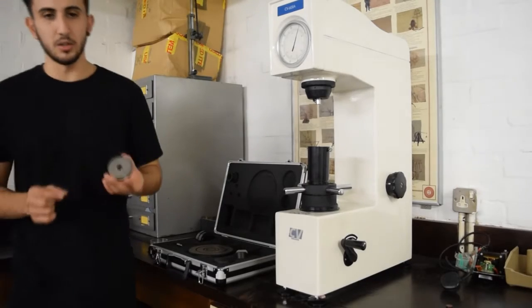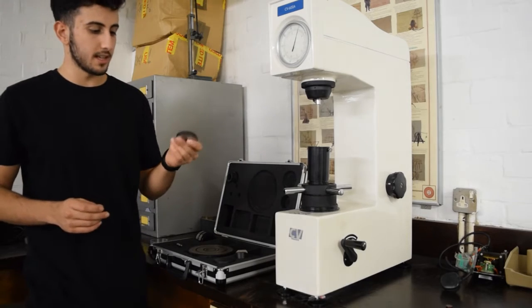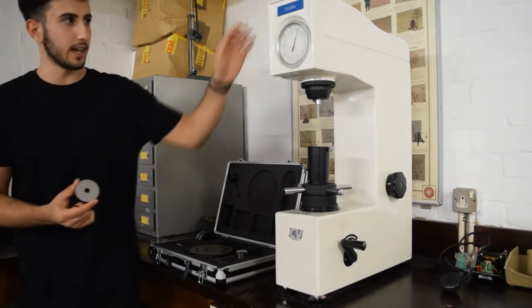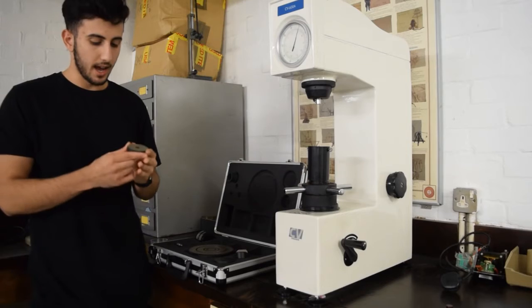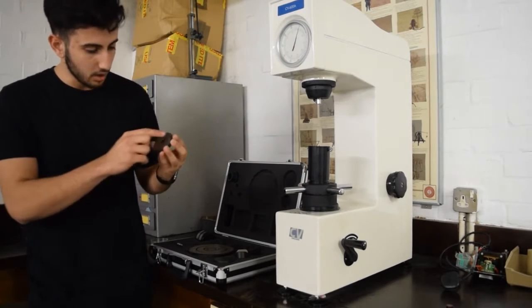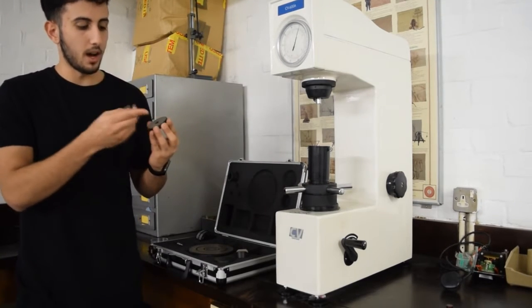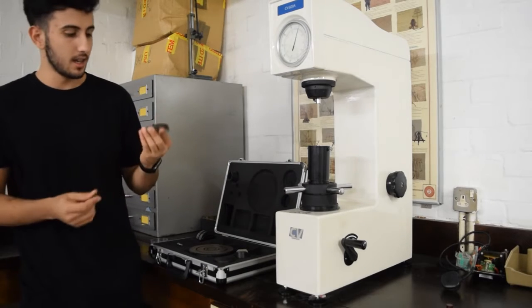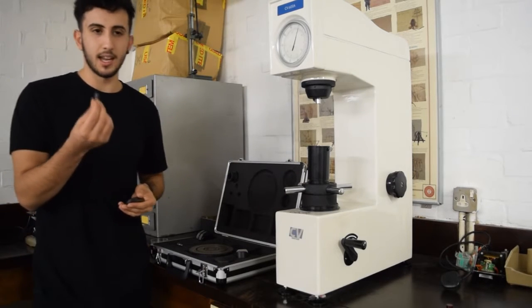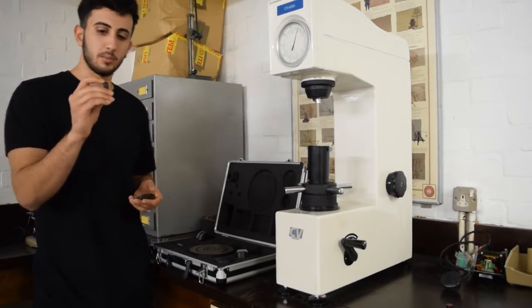Material like mild steel, this is used as a calibration test piece to check that the machine's in working order and is up to calibration. It's got numbers written on here that specifies its actual hardness. This is mild steel, so we'll be using a scale B indenter with a steel ball.